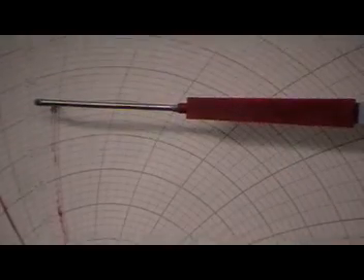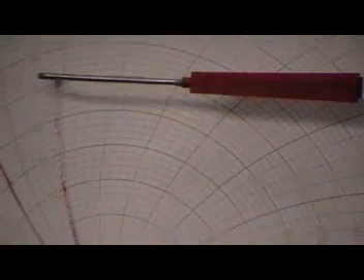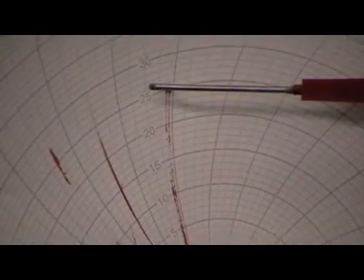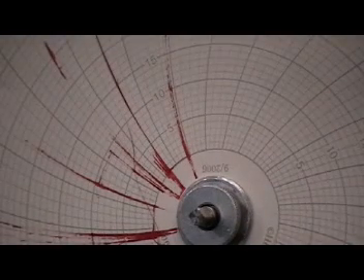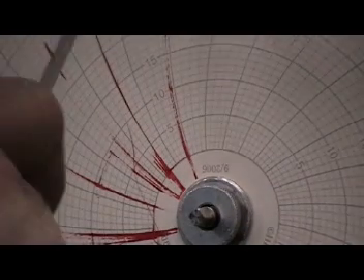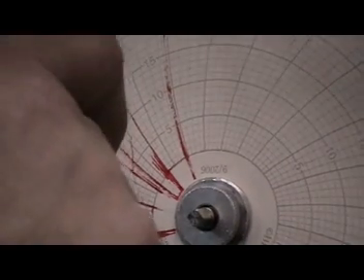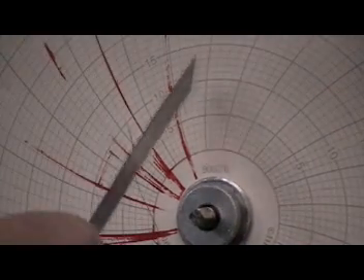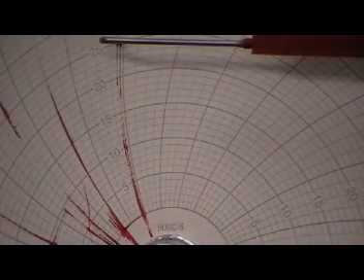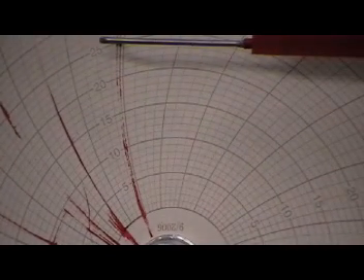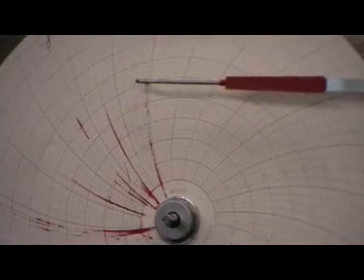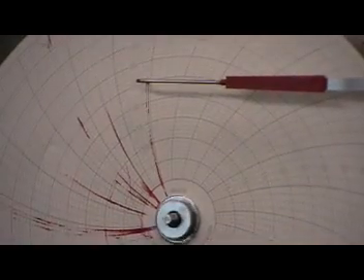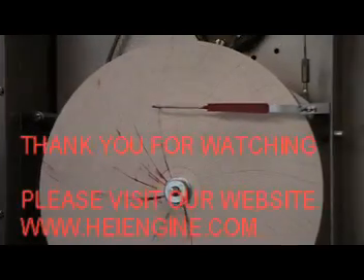It's not possible to calibrate a pressure recorder by doing three pressure movements, because it's possible to have a delinearization problem in the other sectors. The minimum number of points that you need for calibration is 4. We recommend 5. Thank you for watching.